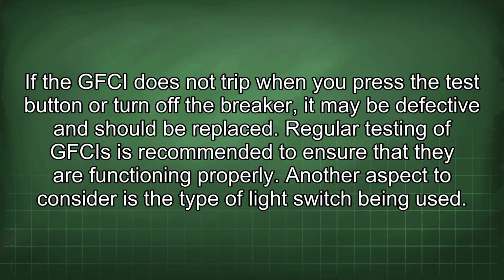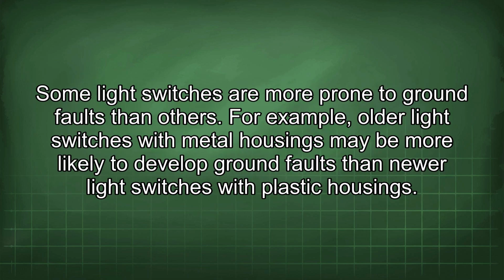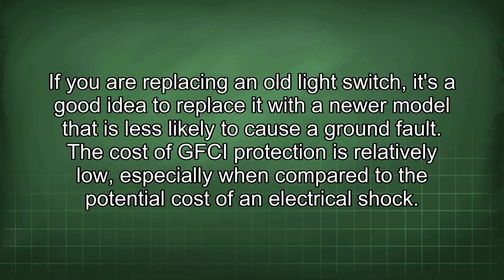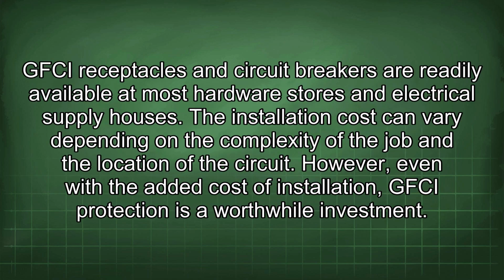Another aspect to consider is the type of light switch being used. Some light switches are more prone to ground faults than others. For example, older light switches with metal housings may be more likely to develop ground faults than newer light switches with plastic housings. If you are replacing an old light switch, it's a good idea to replace it with a newer model that is less likely to cause a ground fault. The cost of GFCI protection is relatively low, especially when compared to the potential cost of an electrical shock. GFCI receptacles and circuit breakers are readily available at most hardware stores and electrical supply houses. The installation cost can vary depending on the complexity of the job and the location of the circuit. However, even with the added cost of installation, GFCI protection is a worthwhile investment.